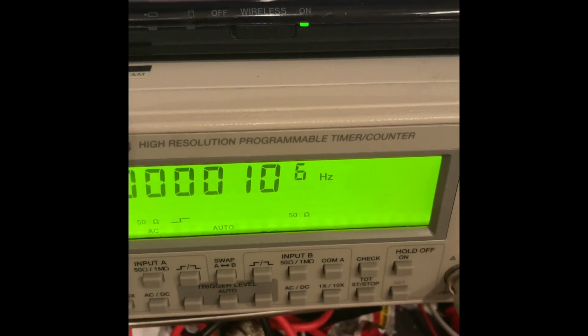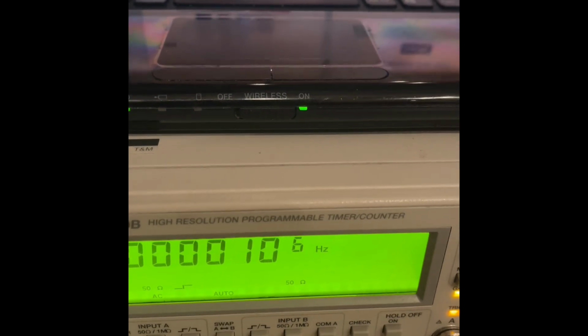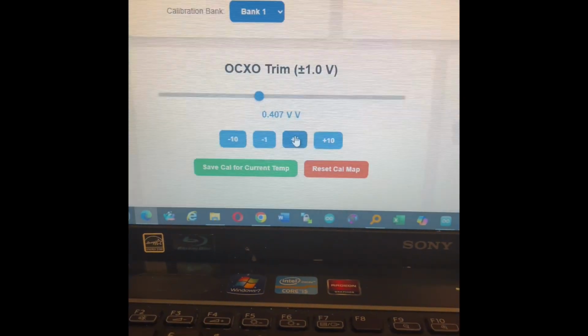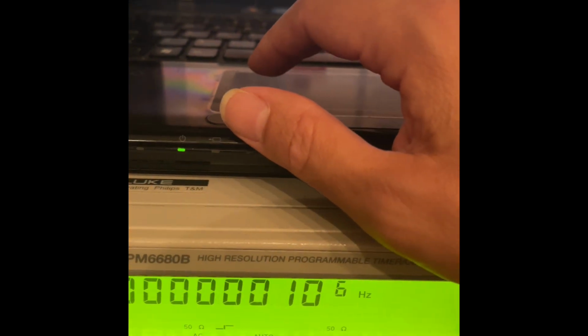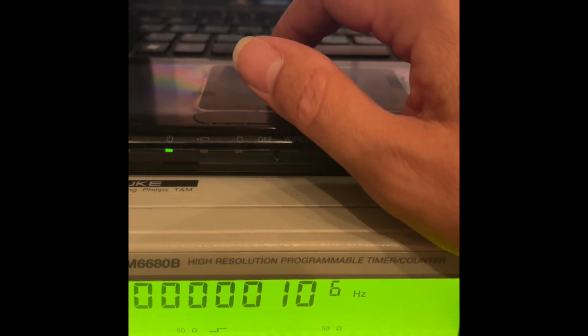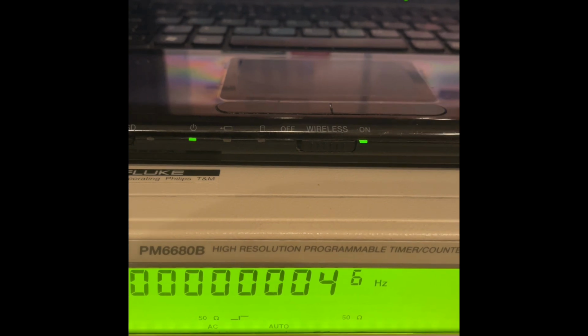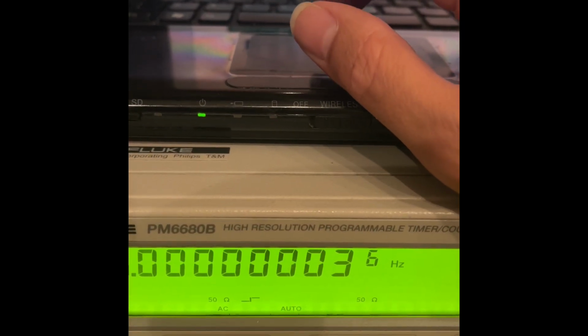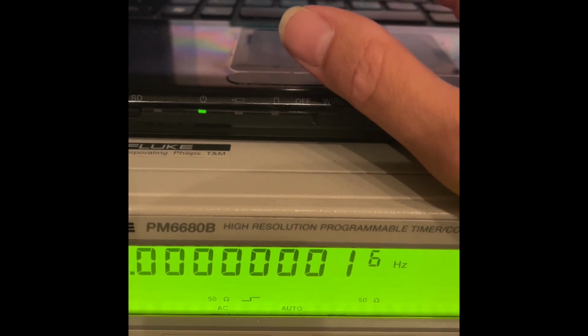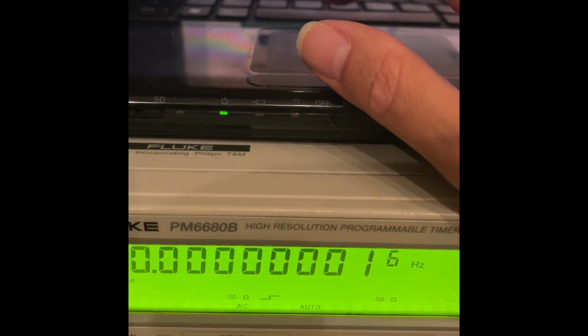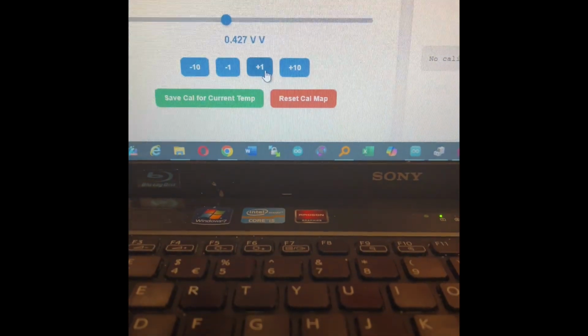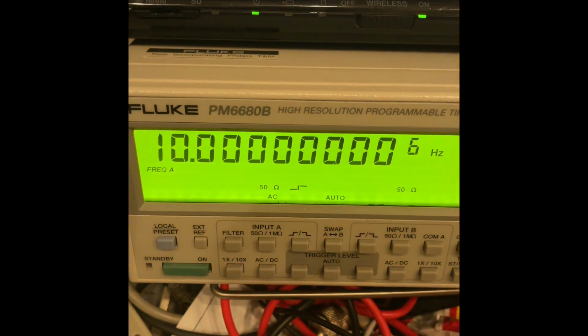So as I say, if you listen to the first part of the videos, then you know that this works on a clamping idea. So if we look, frequency, uptime, got the temperature, which is a work in motion, got our signal here, calibration tables. At the moment there's no calibration set because there's no thermistor connected. But if we go here and we check our frequency, we're going to go up in an increment. So we're going to 408, and it comes down a bit. 409, maybe we need to go up by 10. That's 421. 421, we're nearly there. 422, 24, 25, 26, maybe 27. There you go. So we've got here 0.427, and there we are, spot on calibrated.